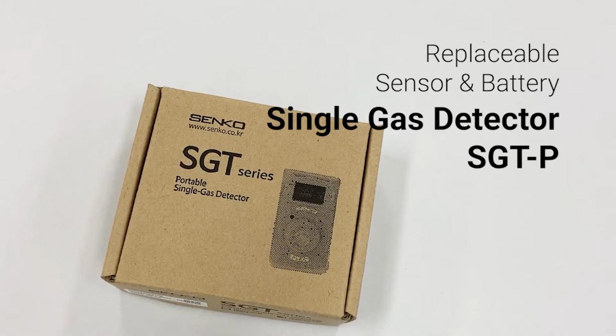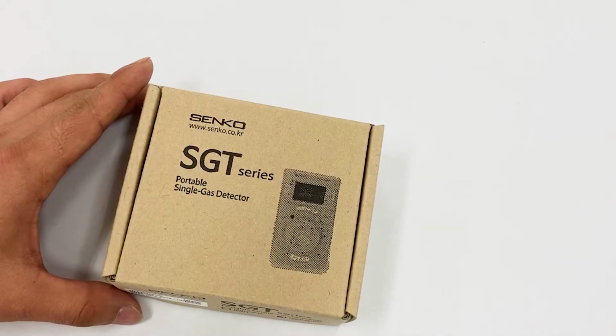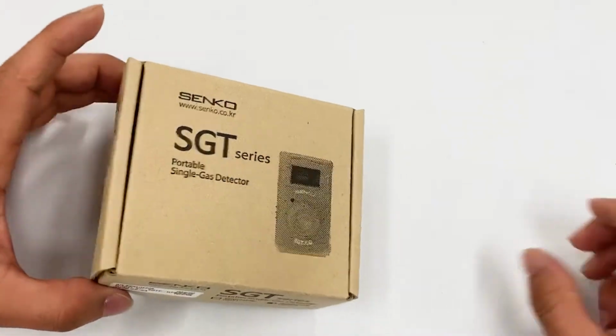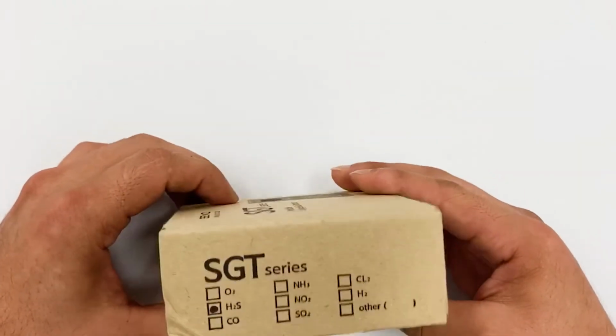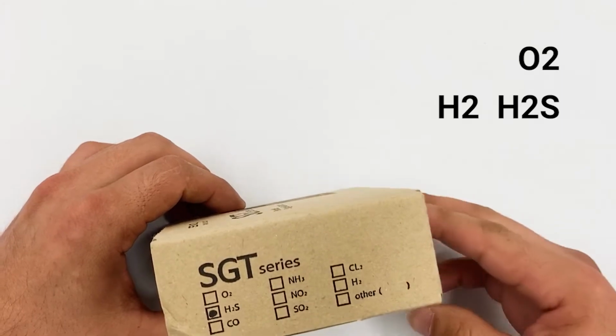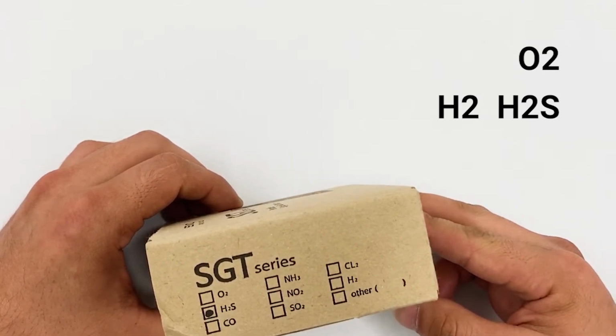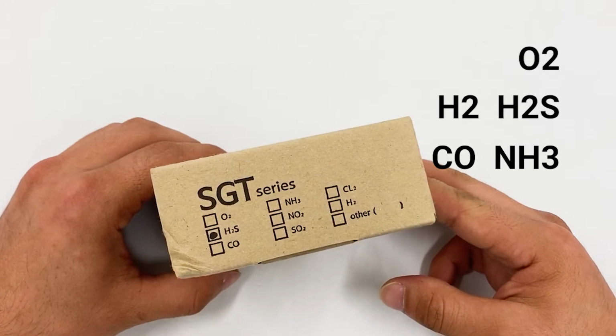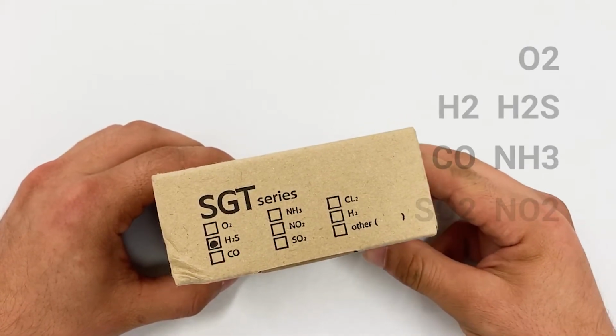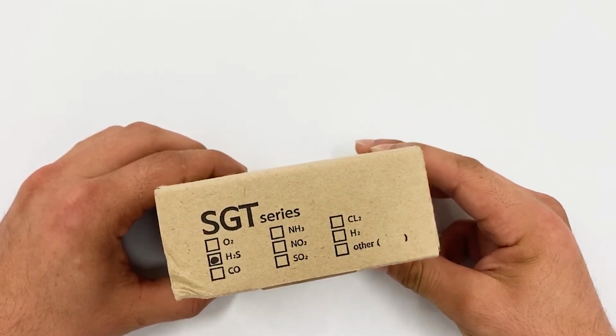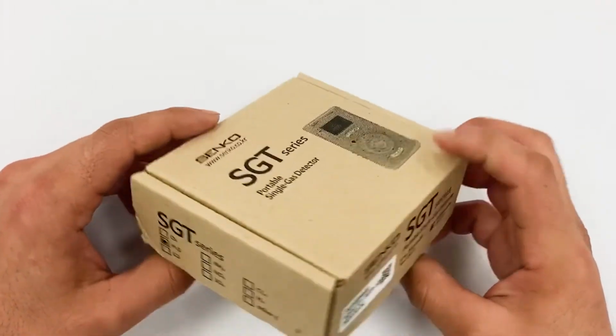SGT-P, a portable and replaceable type single gas detector from Senko. This unit will inform you fast and exact amount of gas existence in the ambient. The gas detection system can be customized to detect and measure one of the 7 optional gases. Those include oxygen, hydrogen sulfide, carbon monoxide, ammonia, sulfur dioxide, and nitrogen dioxide. So let us begin, and I will introduce you basic use of the instrument.